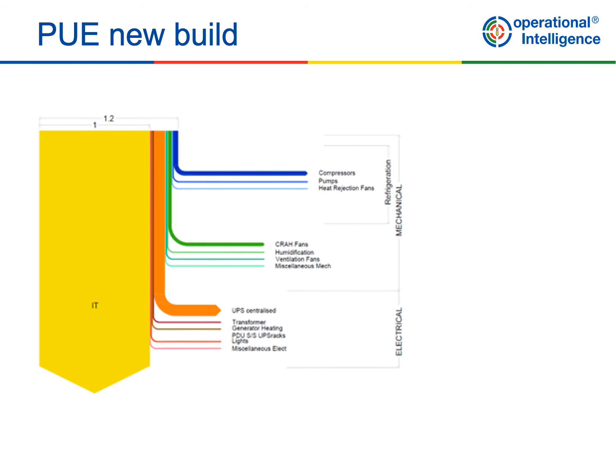For a new build energy efficient facility in Europe, we'd expect to see the PUE a lot lower than this. So making use of operating at higher temperatures and free cooling, we might expect a ratio of more like 1.2, which is a big improvement on some of the legacy facilities.